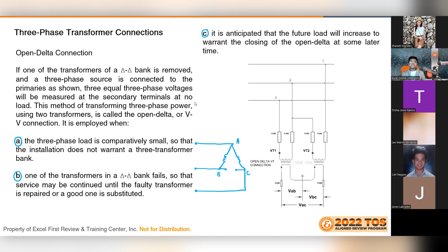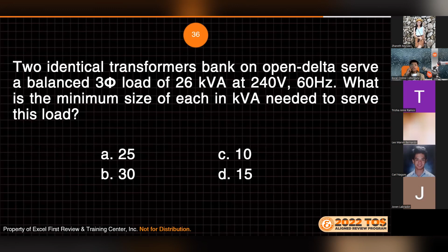Sa open delta naman, itatandaan niyo lang yung mga importanting computation. Okay, proceed tayo. Sabi, two identical transformer banks on open delta serve a balanced three-phase load of 26 kVA at 240 volts, 60 Hz. What is the minimum size of each kVA needed to serve this load? Simple lang ito. Para malaman natin, sa open delta kasi ang kaya niyang i-serve is equal to VV, that's an open delta.